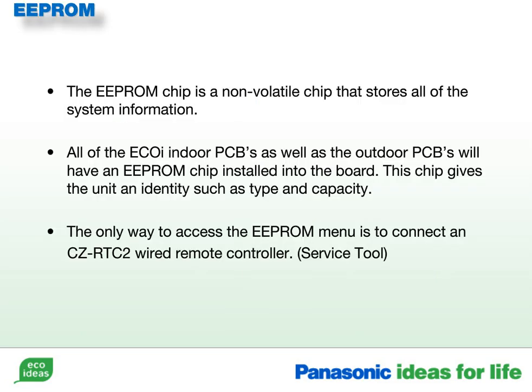All ECOi boards have EEPROM chips on both the indoor and outdoor units. EEPROM chips are non-volatile and they store system information such as unit type, capacities, unit identification numbers and customized settings for your customer's needs or desires. The EEPROM chip can only be accessed with a CZ-RTC2 and the CZ-RE2C2 wired controllers.